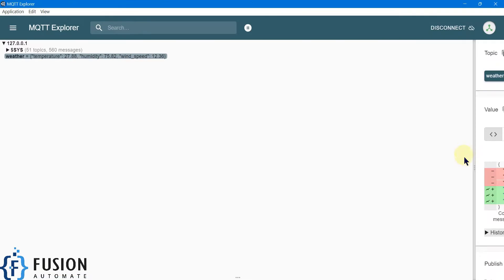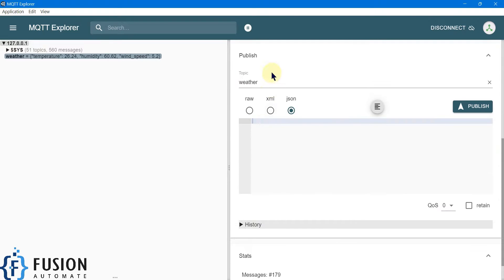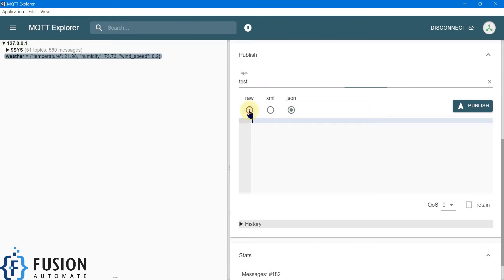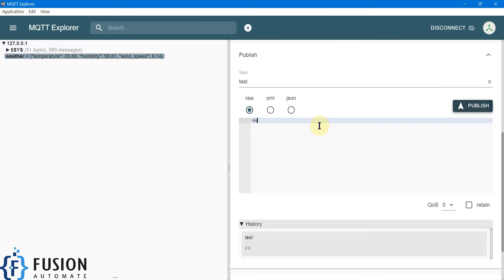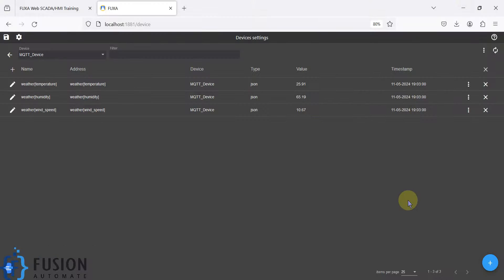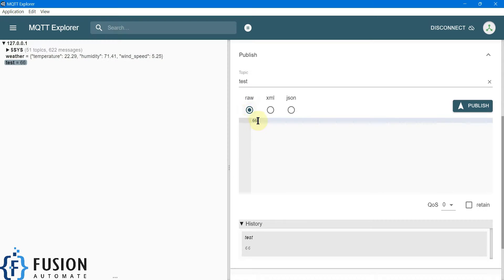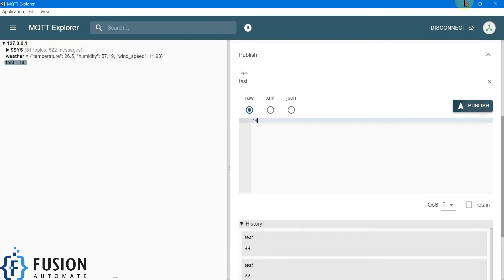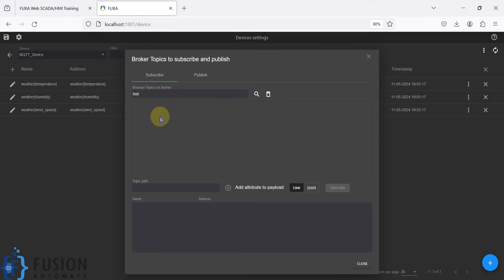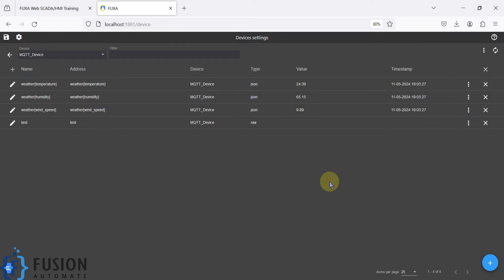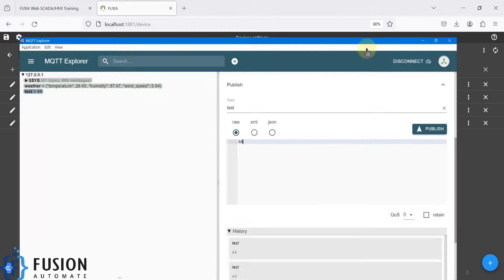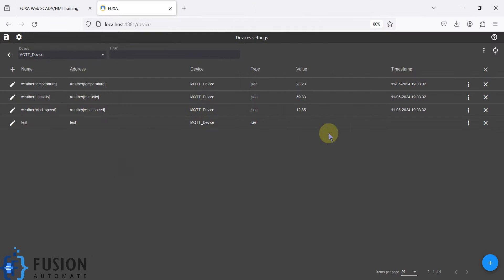If you have a regular payload or raw value — for example, suppose I'm publishing a raw value like 66 to a topic called 'test topic' and I want to subscribe to it in FUXA SCADA — I click the plus icon, provide the topic name 'test', search it, select the 'raw' type, add it, subscribe, and close.